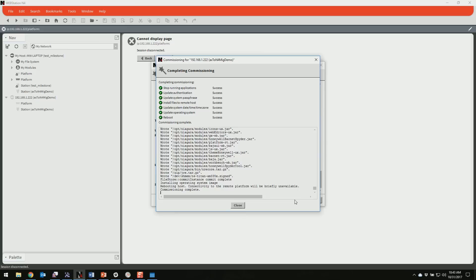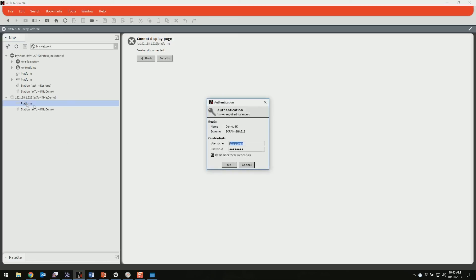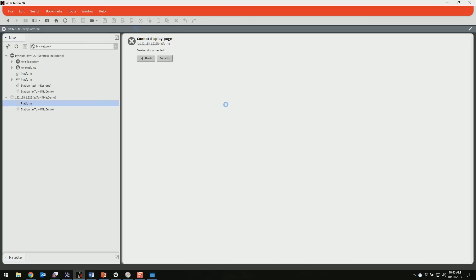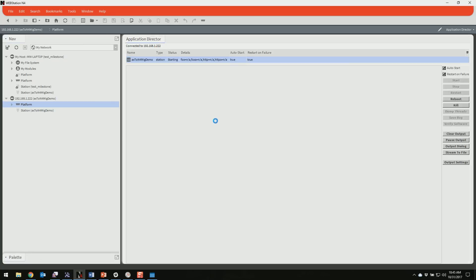All right. The commissioning is complete. So I can hit close here. Going to need to give the Jace a minute or two to come back up. So just wait here and wait for that to come up. All right. So our 8000 is back up. And I can log into it here. And we'll take a peek at the application director and make sure our station comes up. And there's one last step that we need to hit once the station's back up.